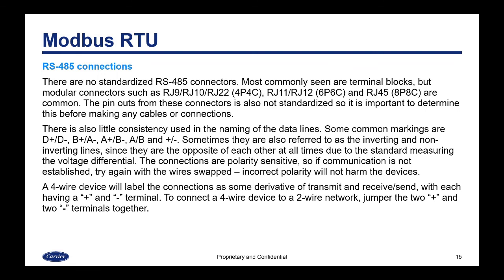The connections are polarity sensitive, so if communication is not established, try again with the wires swapped. The good thing is that incorrect polarity will not harm the devices. A four-wire device will label the connections as some derivative of transmit and receive or send, each having a plus and minus terminal. To connect a four-wire device to a two-wire network, you would jumper the two plus and the two minus terminals together.